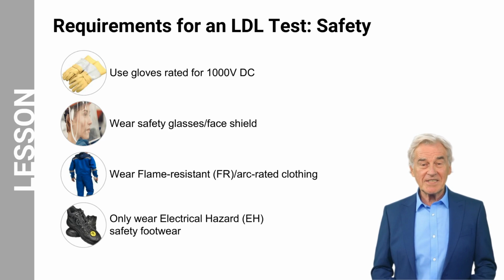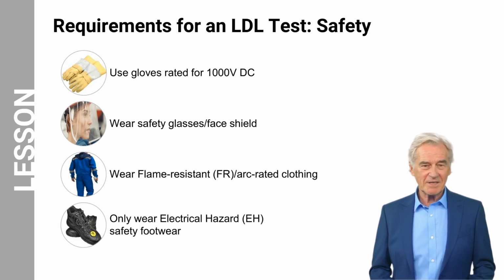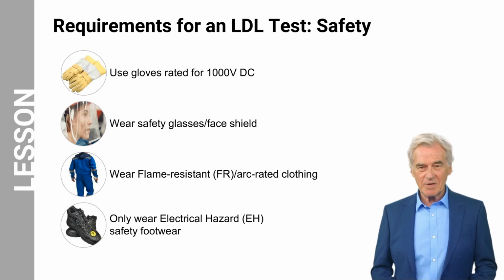Let us now look at the safety requirements to ensure you are safe while performing an LDL test. Wear appropriate personal protective equipment that includes gloves rated for 1000 volts DC, safety glasses or face shield, flame-resistant and arc-rated clothing, and electrical hazard or safety footwear that are critical to ensure your safety. These safety measures help mitigate any risk that may arise while performing an LDL test.